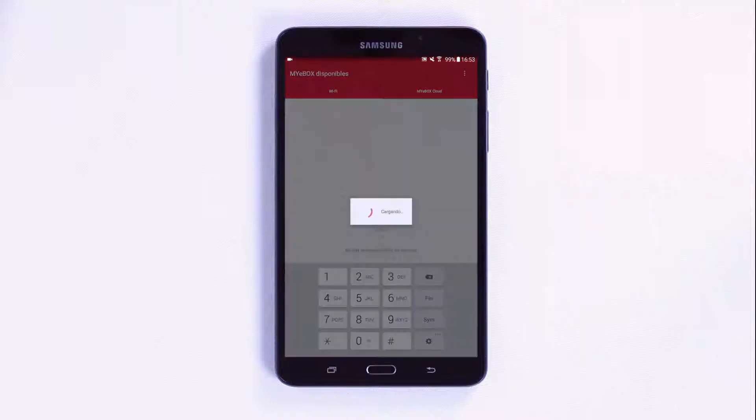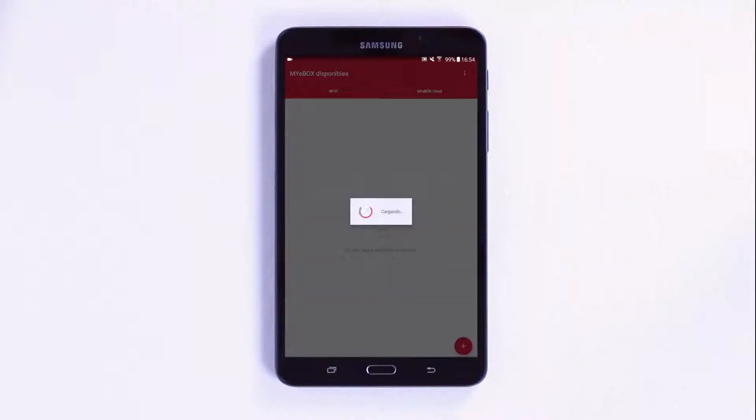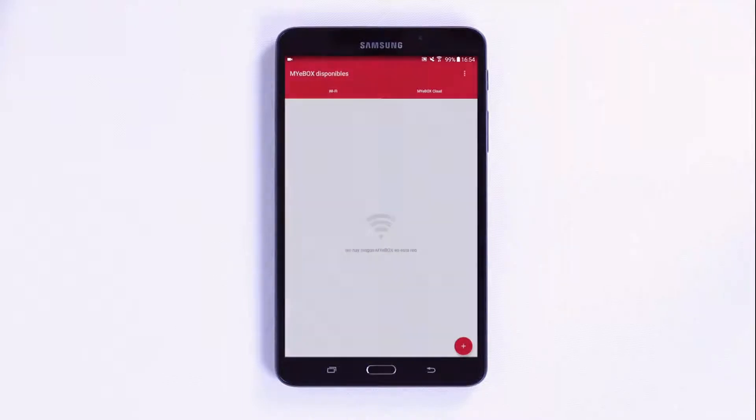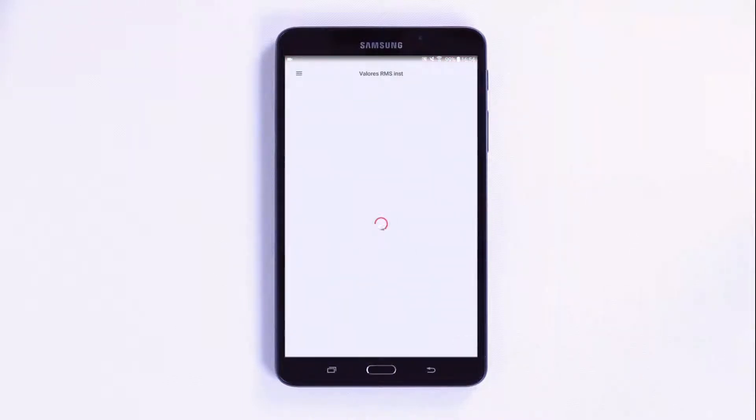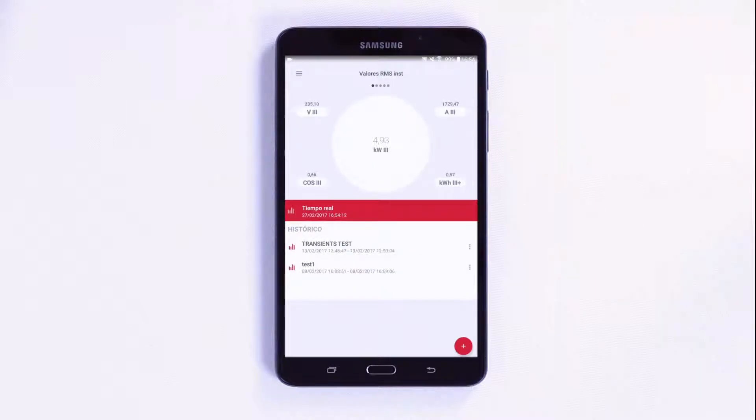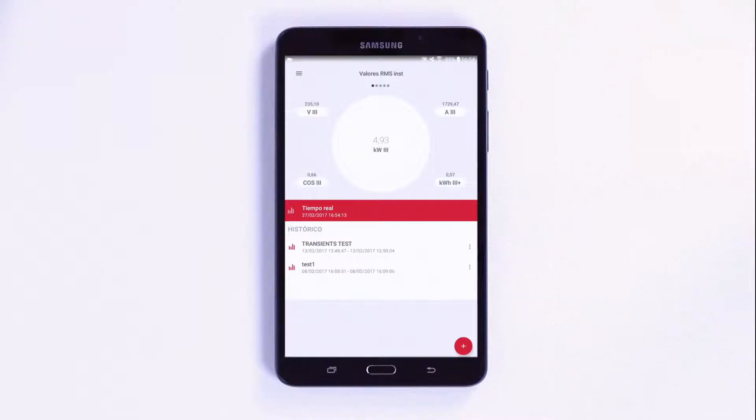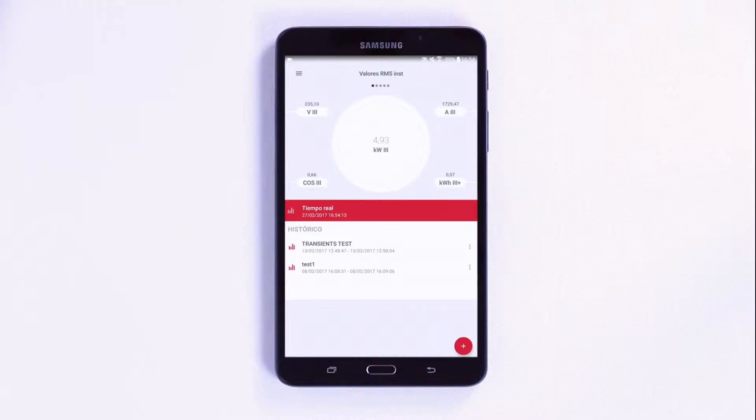Once inside the application, the main screen will be displayed with the installation's instantaneous values and historical values previously recorded in the analyzer's memory. You can also start or stop the recording over new file by pressing the plus button in the bottom right area. It is also possible to access the configuration via the menu located at the top left of the screen.